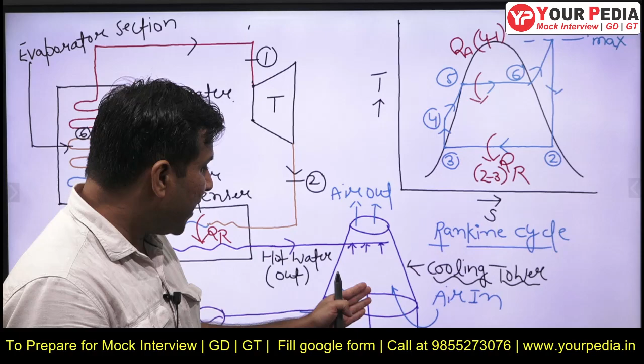Guys, the condenser pressure will increase if we are not able to carry out effective condensation. For example, if your plant is very close to the coastal region, the relative humidity of the air is very high. So in the cooling tower, when we are supplying hot and humid air, that air, because its humidity is very high, is going to take less water vapor with it. बहुत कम वाटर लेगी, because already वो humid है. So effective heat transfer does not take place in the cooling tower. Why? Because the air is already humid air. Saturated air है अगर आपके पास.